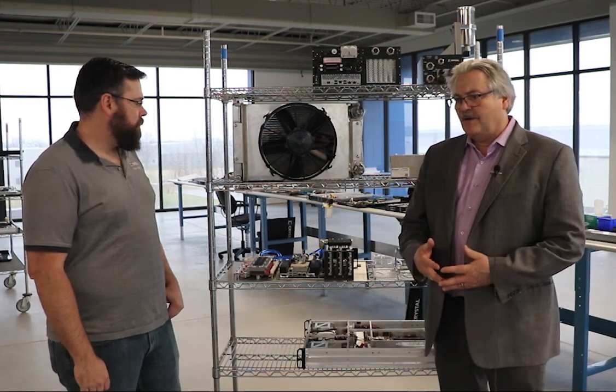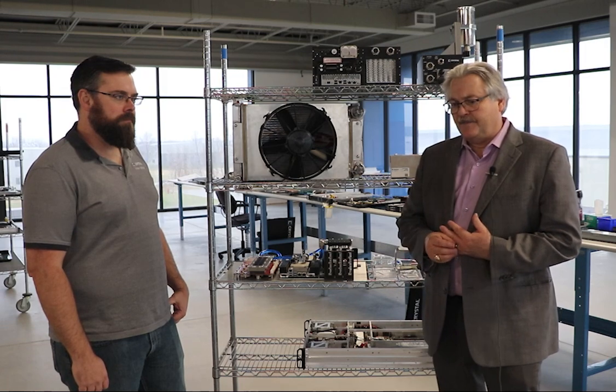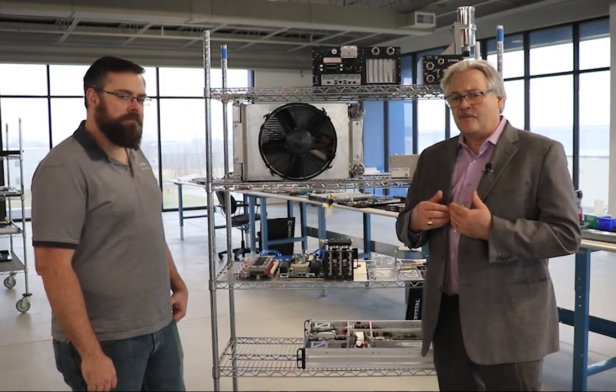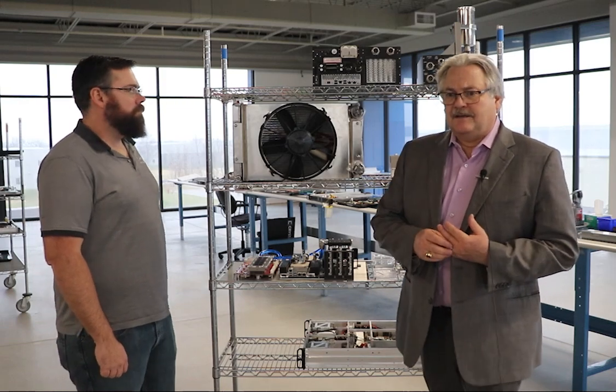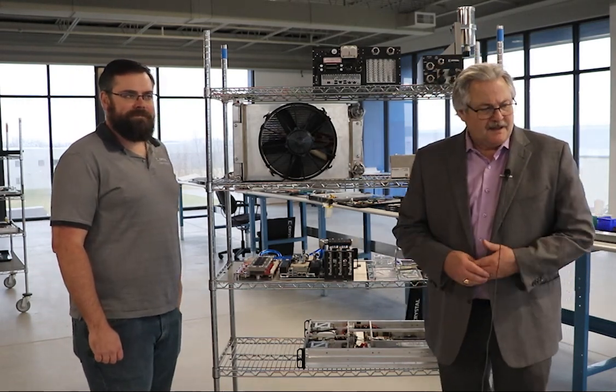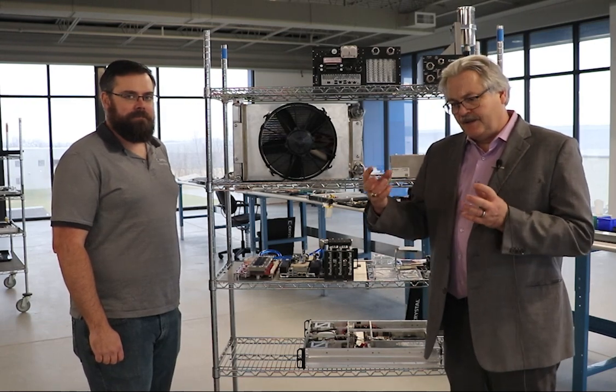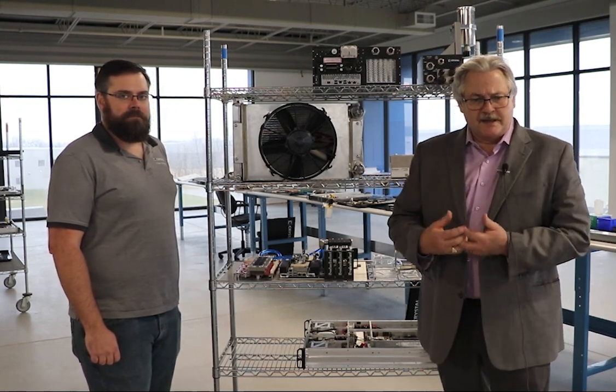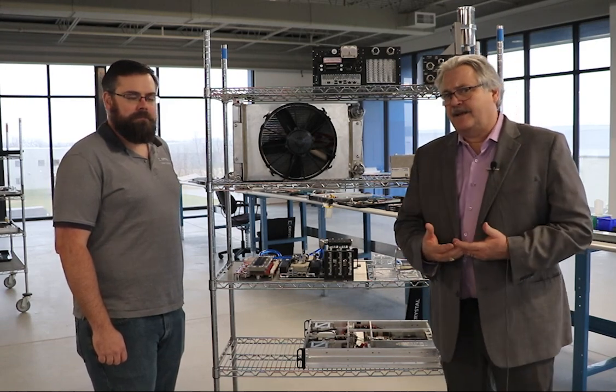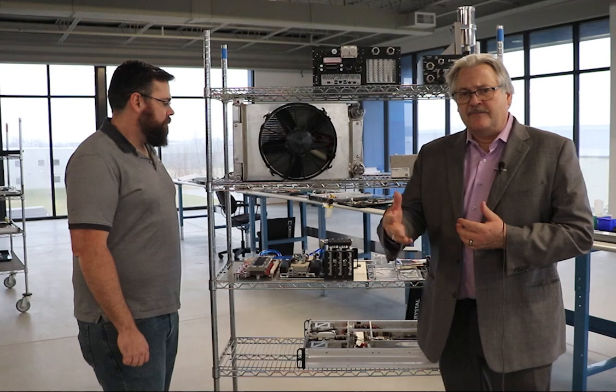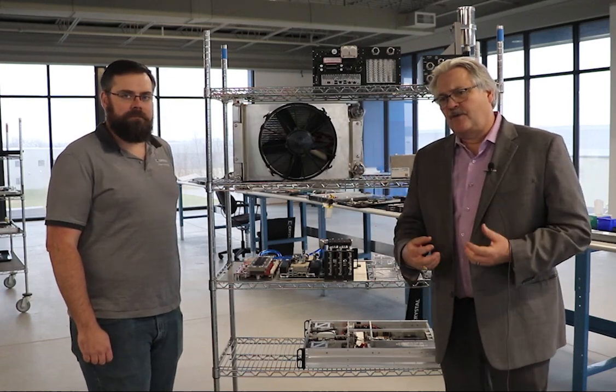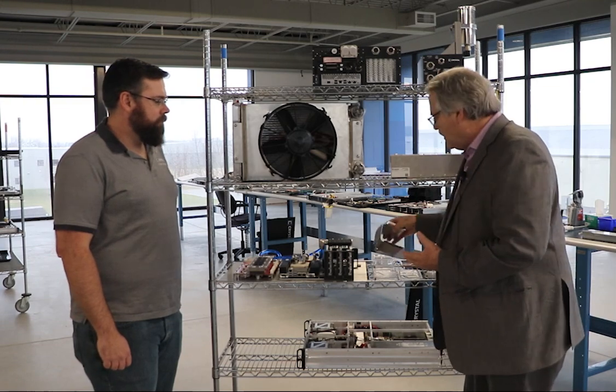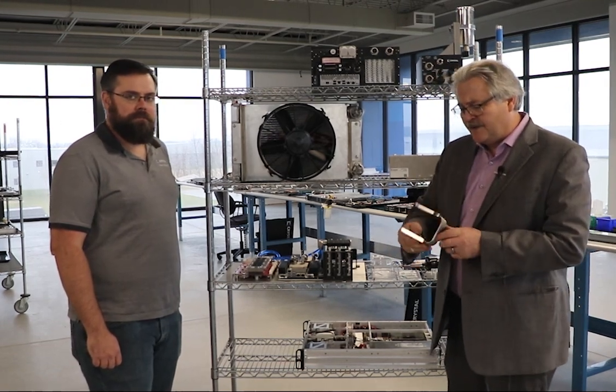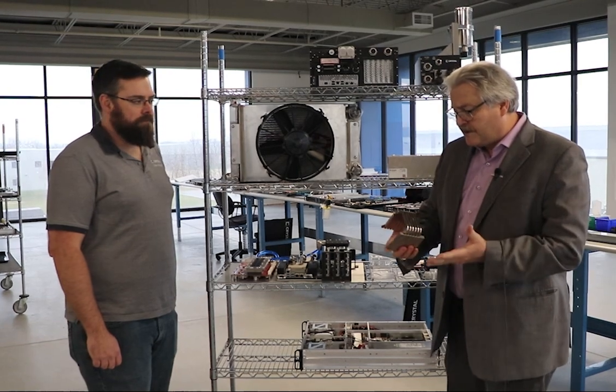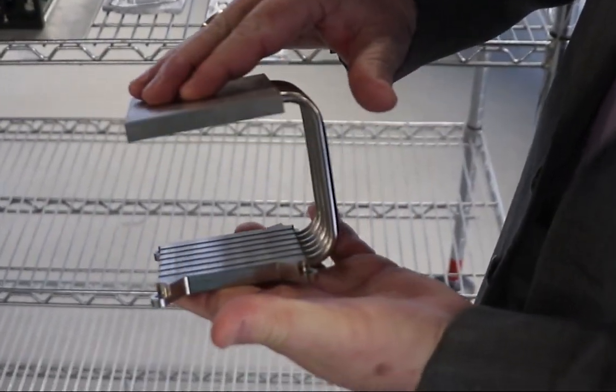One thing we should cover is why we're talking about liquid cooling in industrial or military servers, since generally electronics and water don't mix well. Power densities have become so great that a lot of the previous techniques no longer work. We can't push enough air past, or it requires so much surface area to cool these devices. It used to be that you could do custom heat pipe designs, like this one from a previous design, and that worked, but not so much anymore.